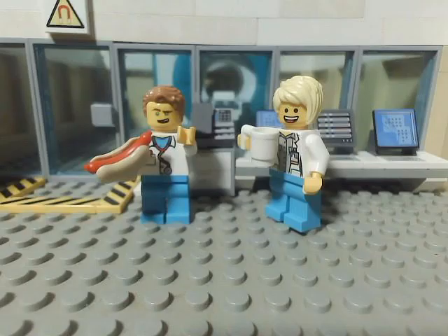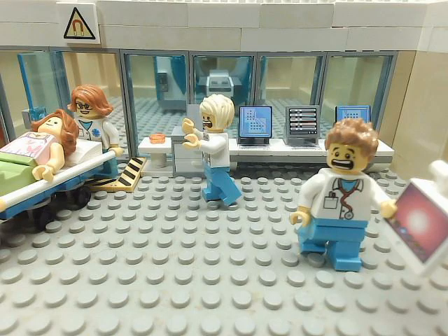The door to the magnet room is important. Only a trained individual can come through that door after they screen themselves for safety, and only a highly trained individual — one with much more training than this video offers — can let someone else through it. We need to make sure that this door is always closed so someone isn't going to go through it.